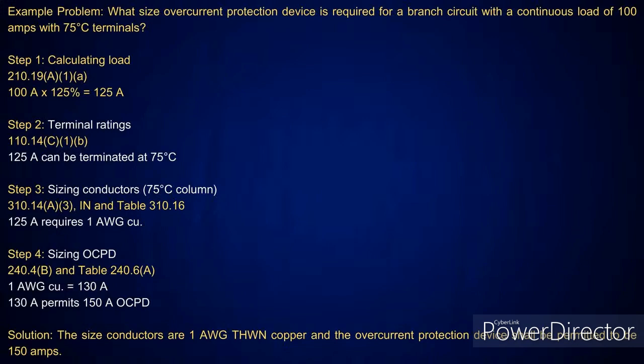Okay. Well, we got a branch circuit that has a continuous load of 100 amps. What do you take it at? 125% gives me 125 amps. The next size above that is 130 amps, and table 310.16 comes across. It's going to tell you it needs a number 1 conductor. I'm going to protect the conductor in this case, which is going to be a 150 amp overcurrent protection device. Now, let's look at this a little bit further. Could I put 100? We'll just leave it at 150 amps.